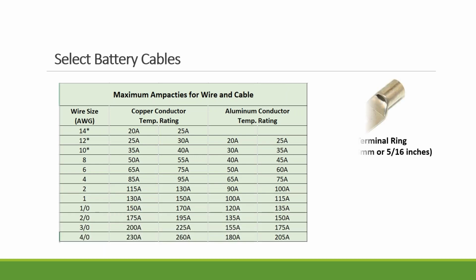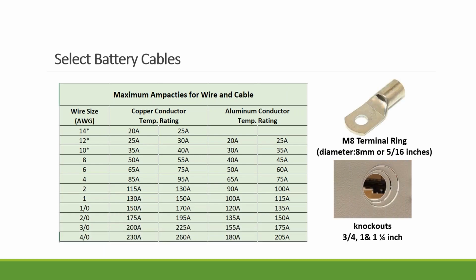Okay, so we're going to cover the installation guide here. If we don't offer the battery cables, you will need to select them, depending on the system size. There's a national requirement for the wiring and cables that you select. Typically, for the small 5 and 10, people will choose 2-gauge, and for the eVolt, people will choose 4-gauge copper wires. The battery has knockouts on both sides, so you can use a conduit to cover all the wires.